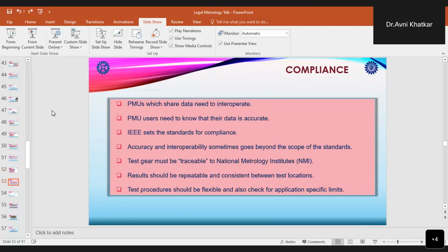So when we talk about this, we talk about compliance also. All these PMUs which share data need to interoperate, and all the PMU users need to know that their data is correct. So IEEE sets the standards for compliance. All the accuracy and interoperability sometimes goes beyond the scope of the standards. So test gear must be traceable to the national measurement institutes, and the results obtained should be repeatable and consistent between test locations. And the test procedures should be flexible, and they should also check for application specific limits.